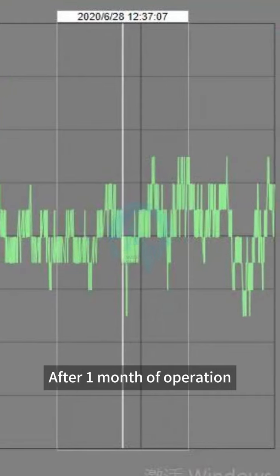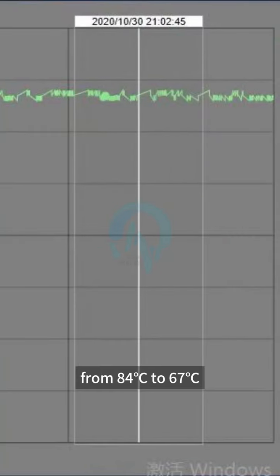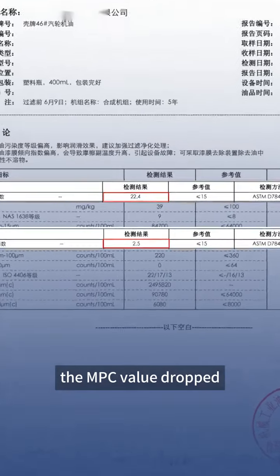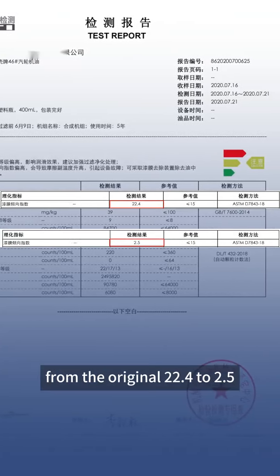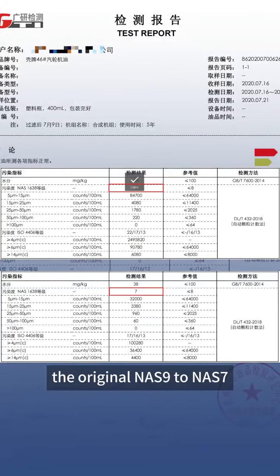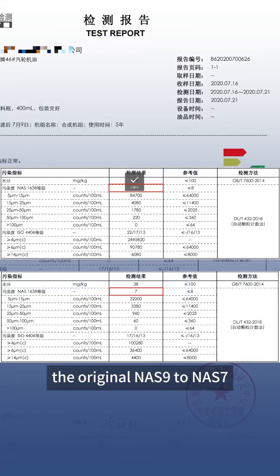After one month of operation, the bearing temperature dropped from the original 84°C to 67°C. The MPC value dropped from the original 22.4 to 2.5. The cleanliness level dropped from the original NAS 9 to NAS 7.